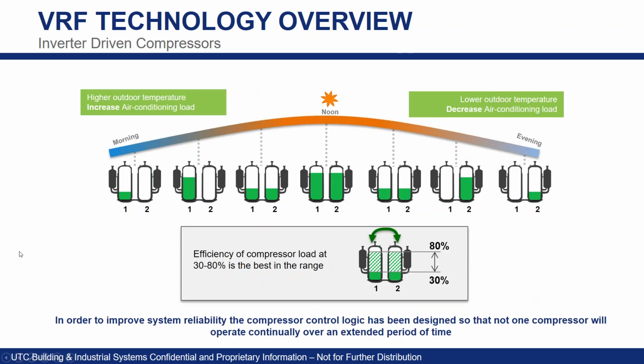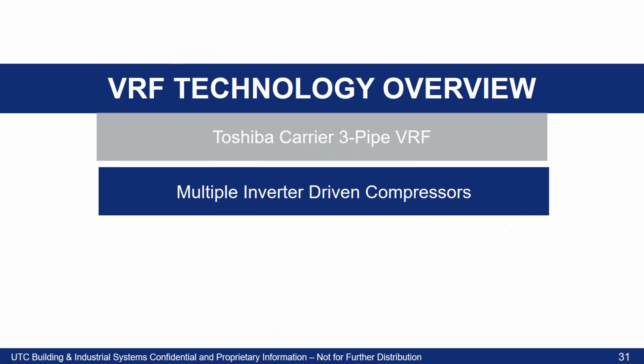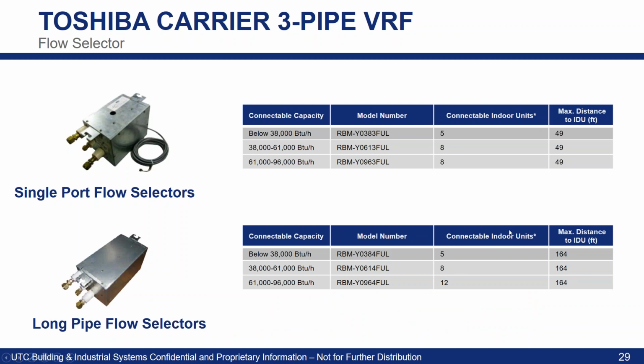Kevin, we did have another question come in. Sure, shoot. From Chun, what are the differences between single port flow selector and long pipe flow selector? Sure, I can go back to that. So really the differences here, Sean, if you just look in this far right column, so that 49-foot mark and this 164-foot mark, that's how much pipe we can hang off of that flow selector, okay? So if you can envision 164 feet of liquid and suction line coming off of that flow selector to the respective indoor unit or fan coil. Sorry guys, throwing a lot of terms here. We use IDU, VRF fan coil, you name it.